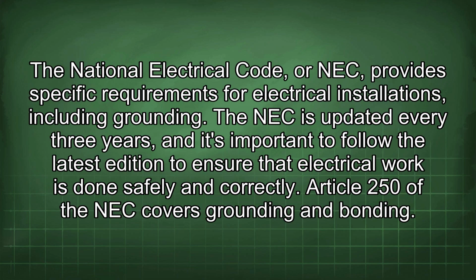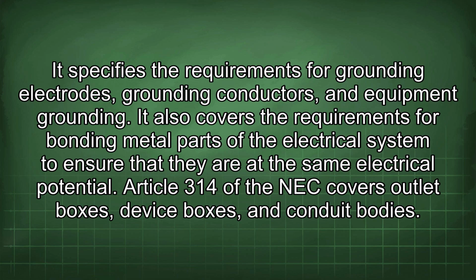The National Electrical Code, or NEC, provides specific requirements for electrical installations, including grounding. The NEC is updated every 3 years, and it's important to follow the latest edition to ensure that electrical work is done safely and correctly. Article 250 of the NEC covers grounding and bonding. It specifies the requirements for grounding electrodes, grounding conductors, and equipment grounding. It also covers the requirements for bonding metal parts of the electrical system to ensure that they are at the same electrical potential.